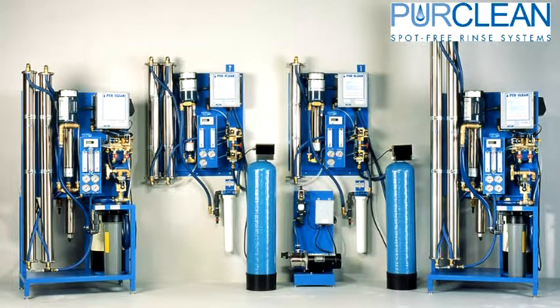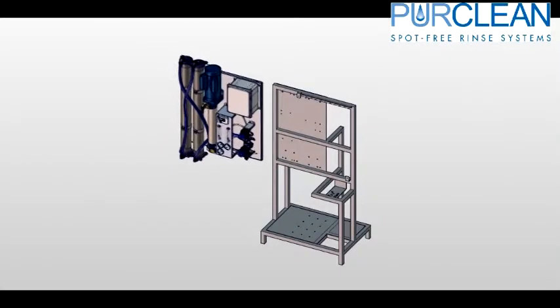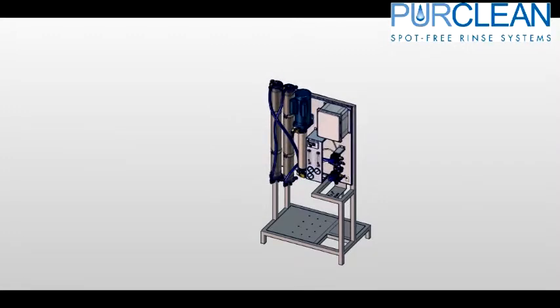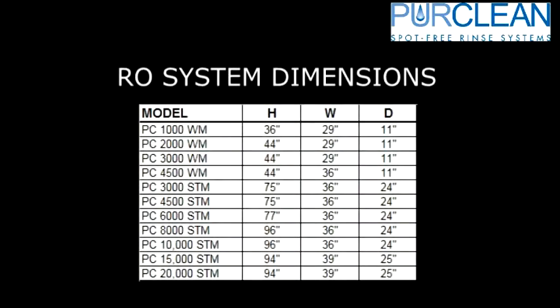PurClean manufactures a wide variety of RO systems. All of our systems are based on gallons produced in a day, or GPD. 1,000 through 4,500 gallon per day systems can be wall or stand mounted, while the bigger RO systems — 6,000 and up — are stand mounted only. Looking at the chart, there are many different variations of space required depending on the size of the RO unit.